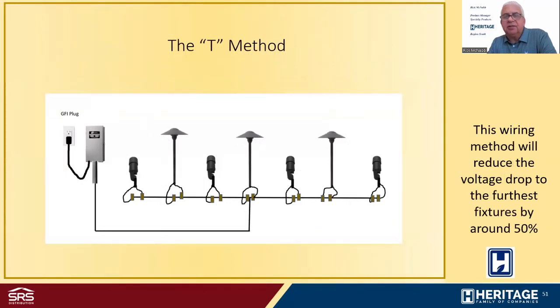Another method is called the T method. In this example, we have, again, the transformer plugged into the GFCI outlet. The wire comes out of the transformer and goes to the center of your wire run, or the center of your lighting circuit. And some lights are fed to the right, some lights are fed to the left from that center point. The advantage of this type of wiring method is that you can reduce the voltage drop to the fixtures by around 50%, because half your wattage consumption is going one direction and half your wattage consumption is going a different direction. So this is a great method to use, and this is also very useful for larger systems like an estate property or even a commercial professional outdoor lighting system.